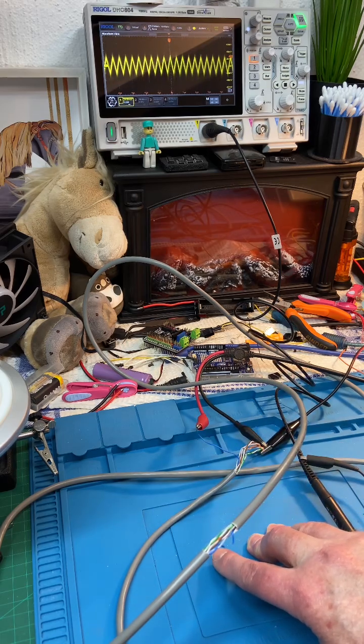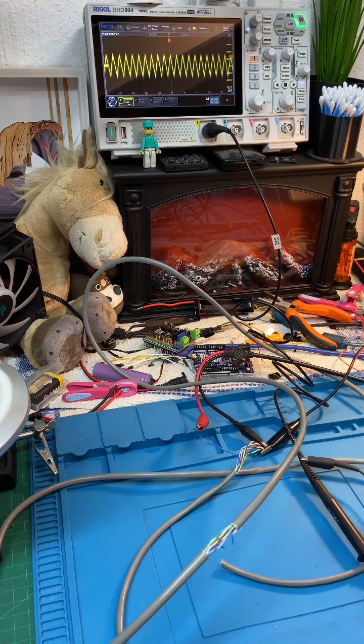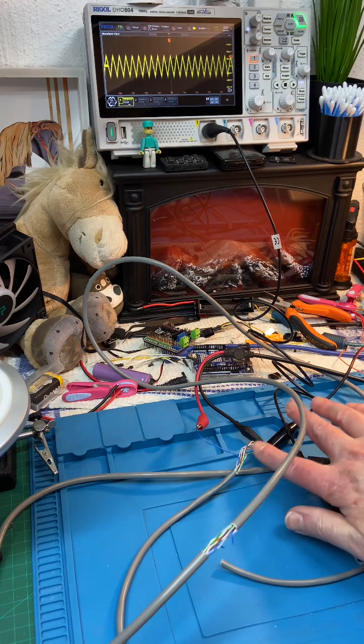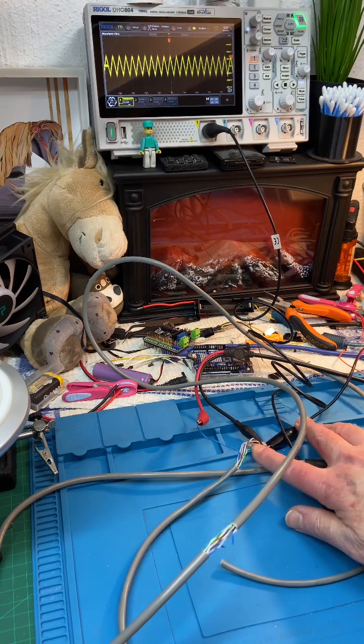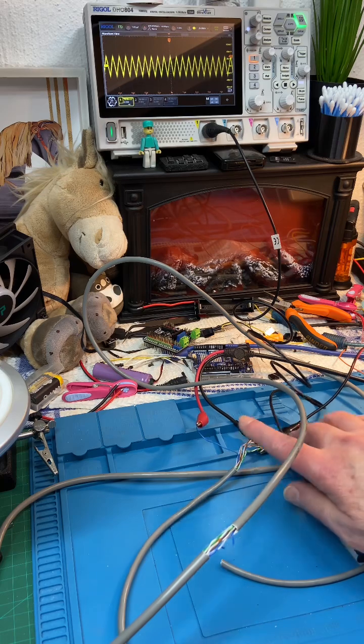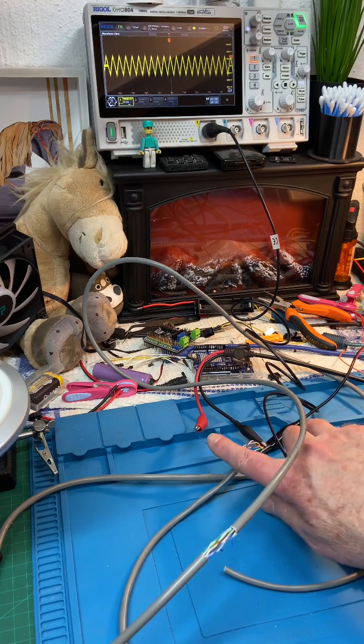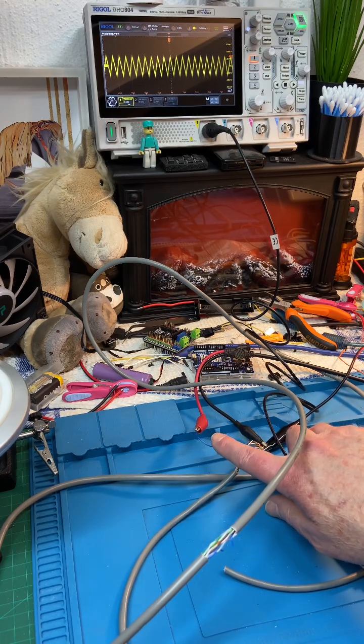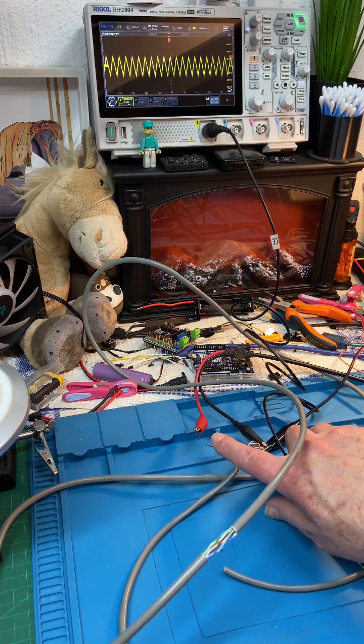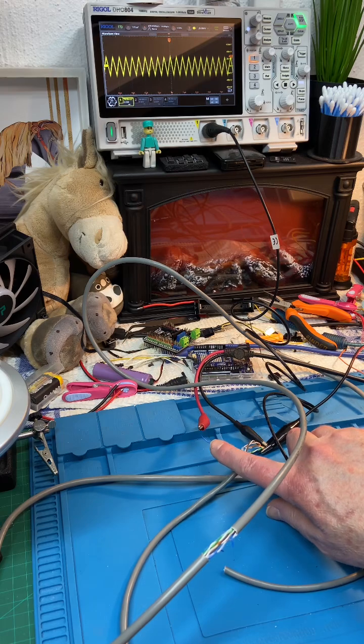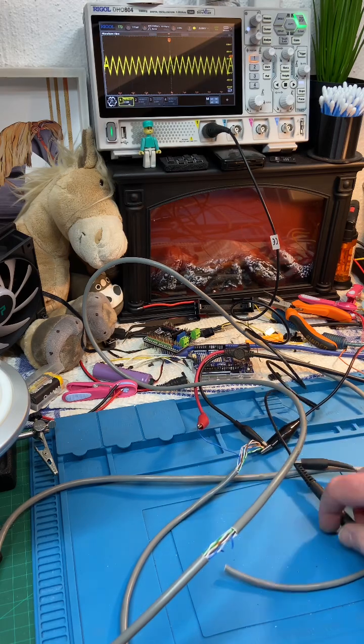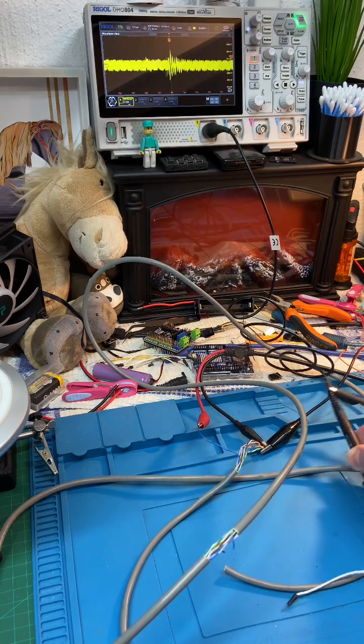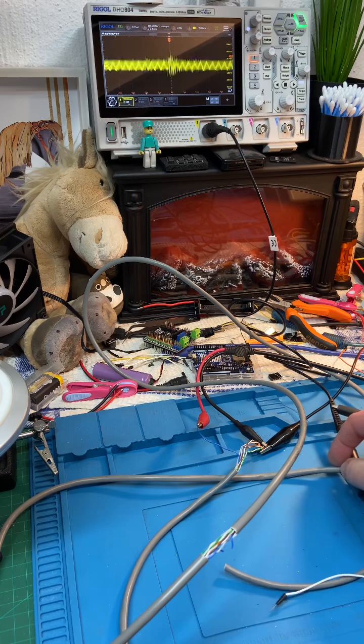So what we've done is over here we've earthed all the remaining cores and we're injecting a two megahertz signal, 50 volts, into the blue wire over there. As you can see over there.